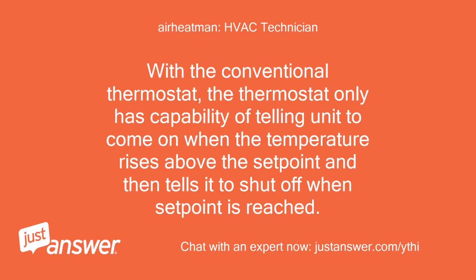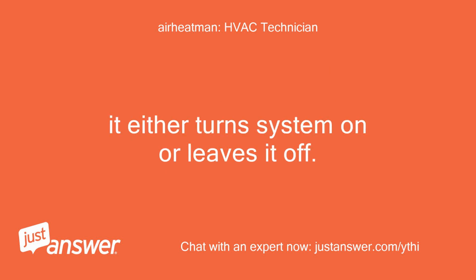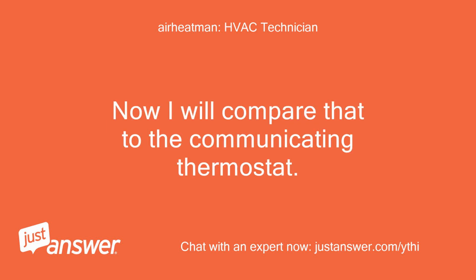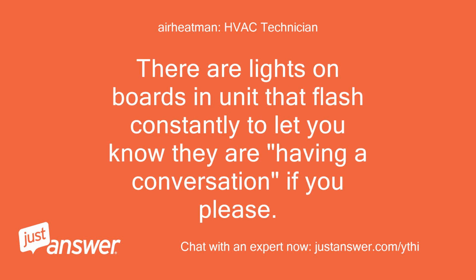With the conventional thermostat, the thermostat only has the capability of telling the unit to come on when the temperature rises above the set point and then tells it to shut off when the set point is reached. Basically like a light switch controlled by temperature. It either turns the system on or leaves it off. Now I will compare that to the communicating thermostat. With the Infinity, the thermostat, air handler and outdoor unit are like buddies talking back and forth. There are lights on boards in the unit that flash constantly to let you know they are having a conversation, if you please.